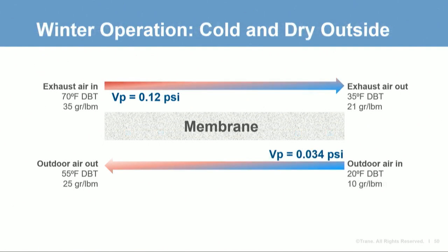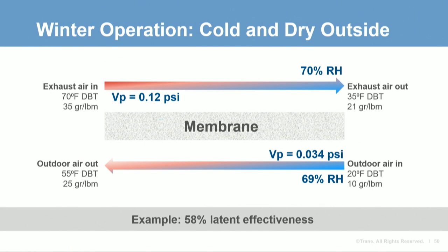During heating, the water vapor pressure is higher on the exhaust airstream, so water vapor is recovered from the exhaust air to the outdoor air. The more saturated the membrane is with water vapor, the higher the transfer rate through the membrane. The relative humidity of the exhaust and outdoor airstreams is higher in winter, resulting in a more saturated membrane and higher transfer rate. For this example membrane, the latent effectiveness increases to 58% in winter.